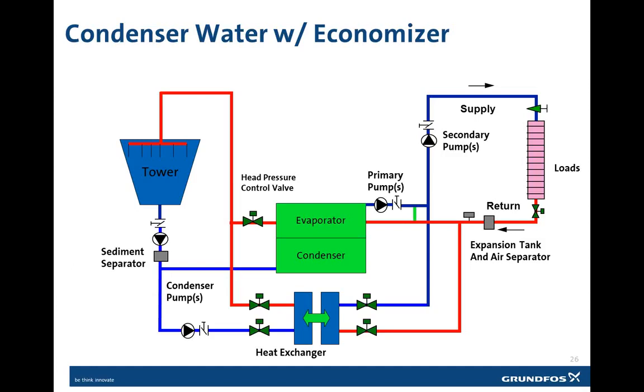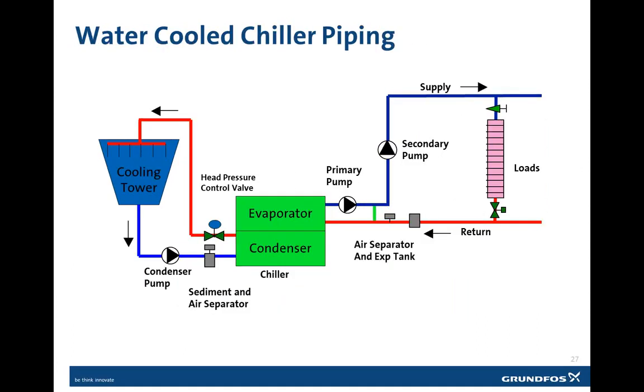Now, the addition of an economizer loop can also add additional pumps to the systems. So as shown here, now we have our economizer loop in the bottom with our heat exchangers. Now, a water-cooled chiller requires that there be a heat rejecting piece of equipment that's located outdoors. So in this case, it's the cooling tower. And again, this piece of equipment is connected to the chiller's condenser, creating the condenser water loop.